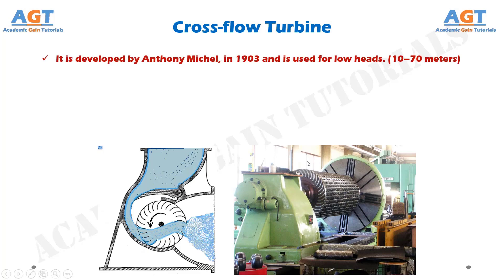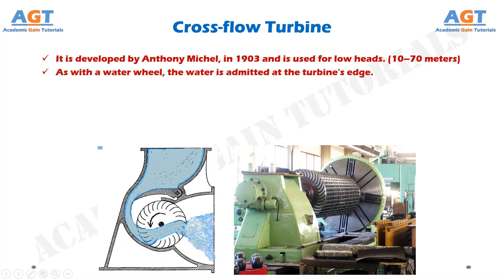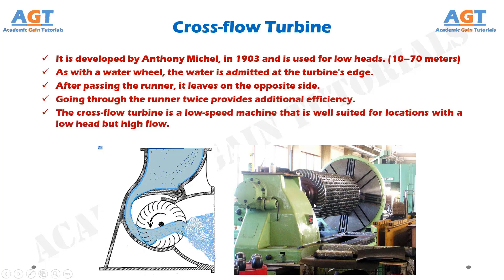The cross flow turbine is another type of impulse turbine. It was developed by Anthony Michel in 1903 and is used for low heads of 10 to 70 meters. As with the water wheel, the water is admitted at the turbine's edge. After passing the runner, it leaves on the opposite side. Going through the runner twice provides additional efficiency. The cross flow turbine is a low speed machine that is well suited for locations with a low head but high flow.